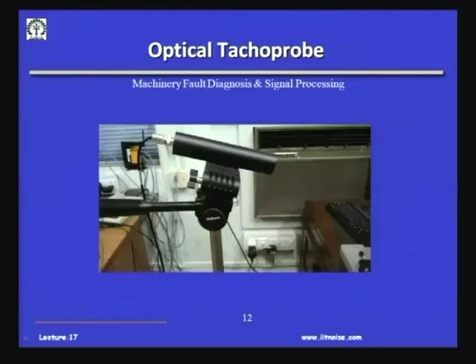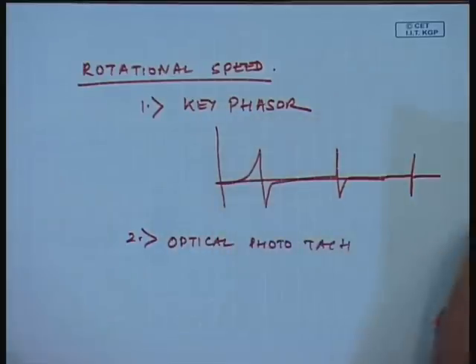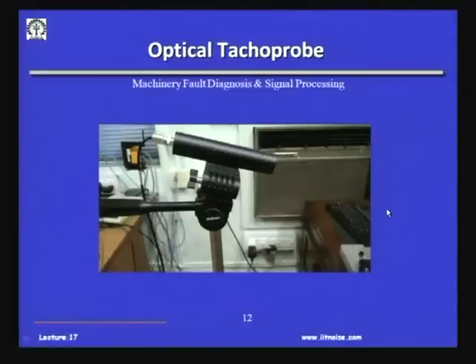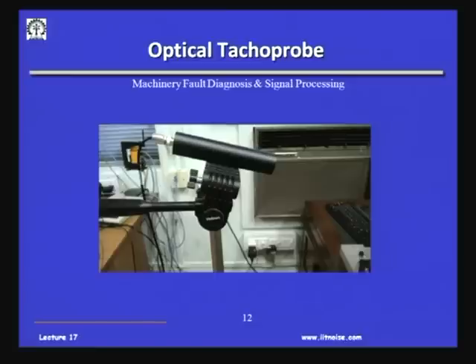The next is the photo tacho wherein an optical light is given, and on the shaft a reflective tape is put. Every rotation this reflective tape comes just below the transmitted light and reflects it back - so you get a light pulse back. From the electronics you can measure the time distance between transmitted and reflected pulses to know the time taken for one rotation. Unlike mechanical tachometers where pressing on a shaft can reduce shaft speed, photo tachos are non-loading and have a very fast response time. You could measure speeds as high as 50,000 RPM.